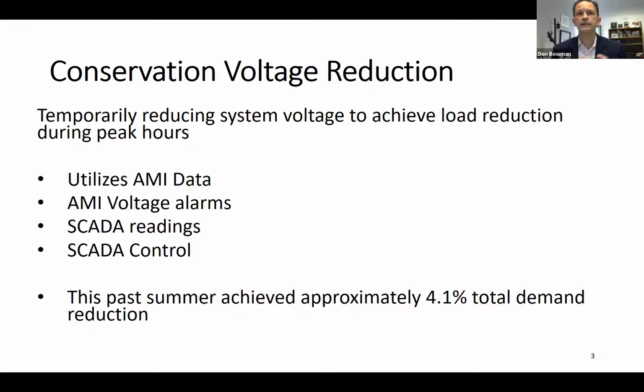We utilize AMI data, meaning every meter gives us real-time voltage readings, letting us know if we've surpassed thresholds for poor power quality. The ANSI standard says we can't go below 114 volts at a house, so every meter tells us if we've gone below that. If so, our system backtracks to correct power quality, with every feeder and zone treated separately for maximum effect.